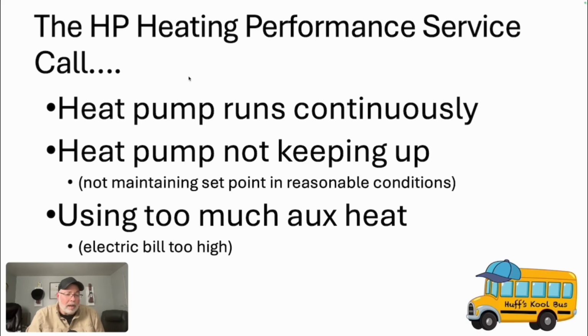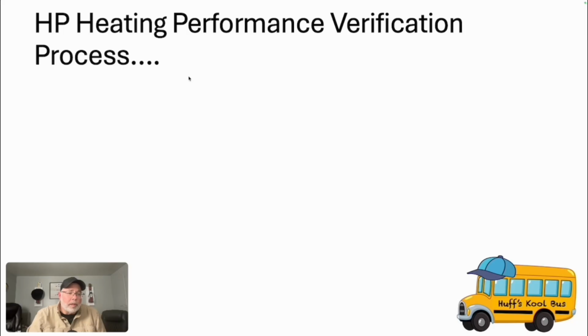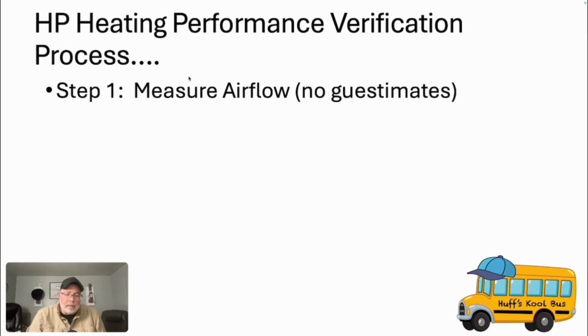Either way, we need to figure this out. We need to find out what it's doing, what it should be doing. And so I'm going to share with you this three-step process, if you will. So step number one, measure airflow. No guesstimates. Why do we want to measure airflow? Well, first off, we can't determine our delivered capacity without measuring airflow. Airflow is part of the equation.